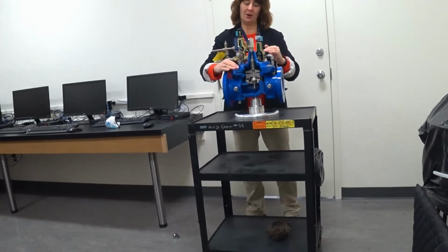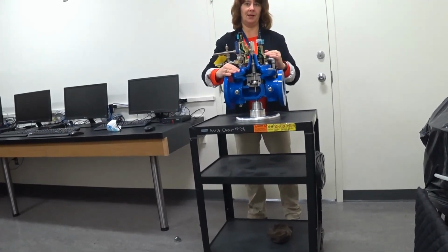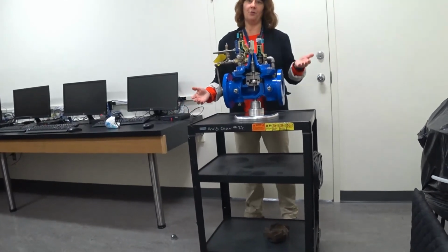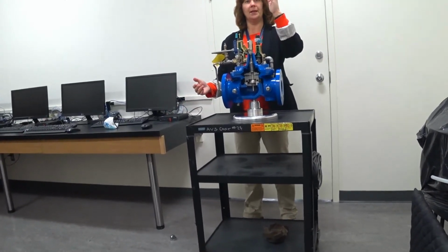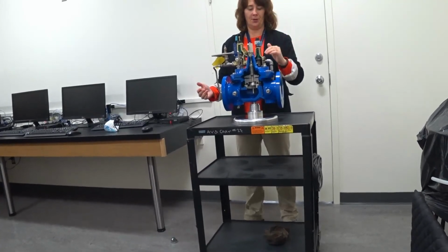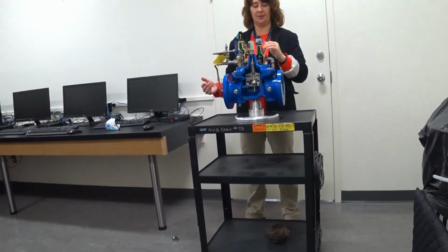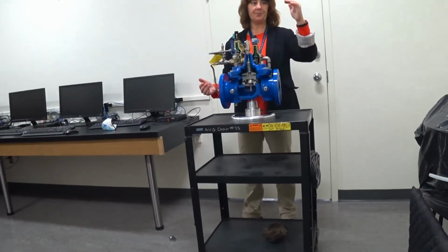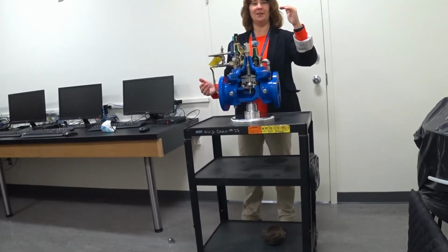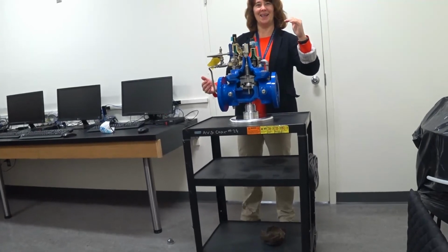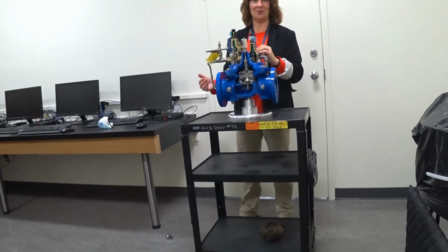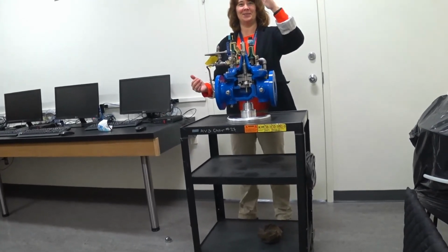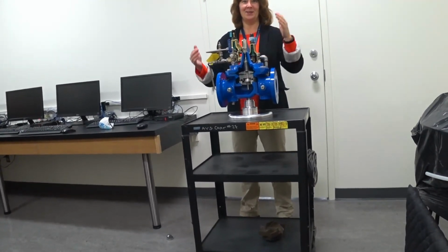And when we talk about opening and closing, it's not like open and close all the way through the full range. We're talking modulating around a set point. So if this is set at trying to maintain a 60 psi downstream pressure, the pressure will maybe drop down to 59, 58, 57, and this will start to do its business, or it will creep up to 61, 62, 63 psi, and again, we'll start to regulate.